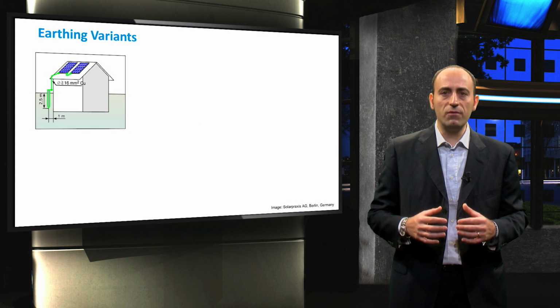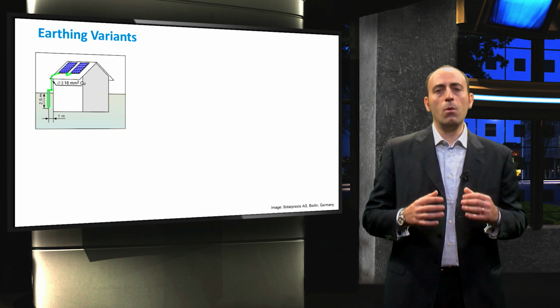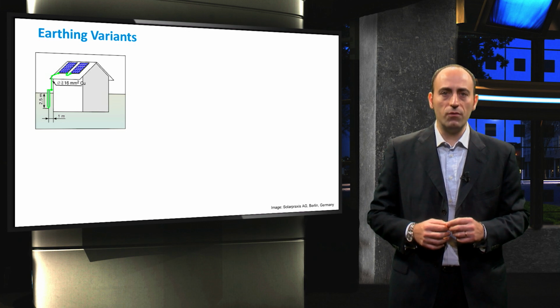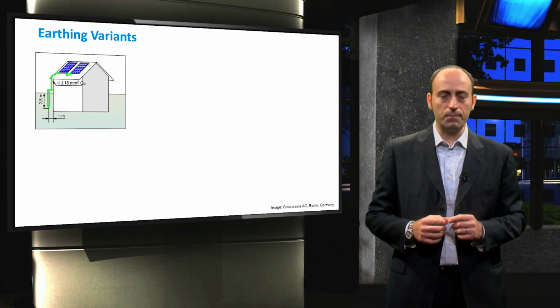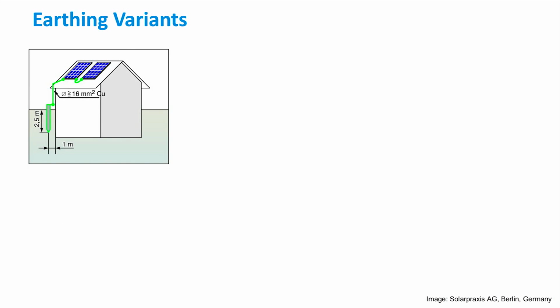Since it would not be safe to keep it electrically floating, we are going to present 4 types of earthing systems for PV systems. In green, the circuit protective conductors are depicted. Their task is to join together all exposed conductive parts and connect them to the main earthing terminal. For example, a very easy option is to connect the aluminum frame of all the modules in series and then connect everything to a metallic rod, which by law has to be at least 2.5 meters deep in the ground and 1 meter away from the building.